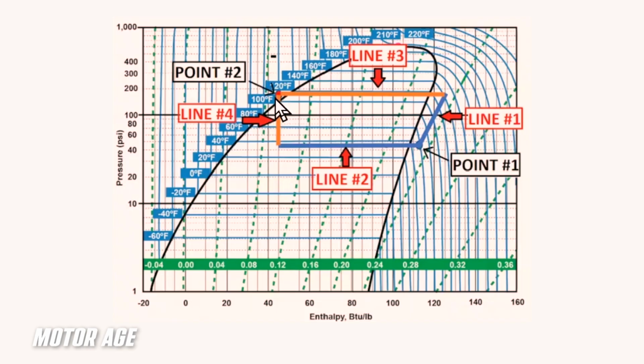Because it's to the left of the bell curve here, it's proving it's a saturated, fully saturated liquid, which is desirable because we need the liquid refrigerant as such so it can evaporate and absorb heat. If it stays within this bell curve, it is not yet a liquid, meaning it doesn't have the ability to absorb as much heat, as many BTUs, as it would if it was a fully saturated liquid. So that's what we should expect to see from a healthy system.